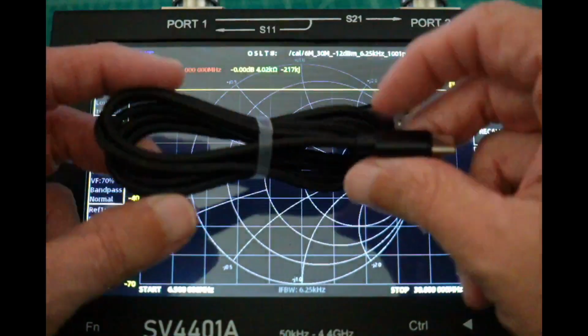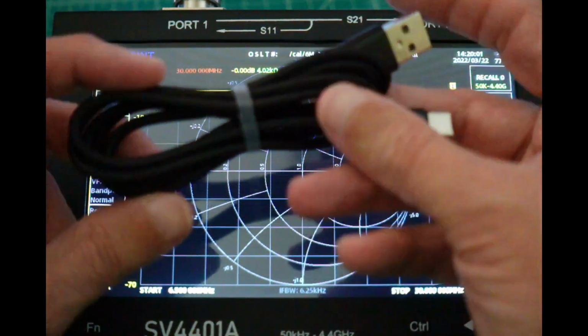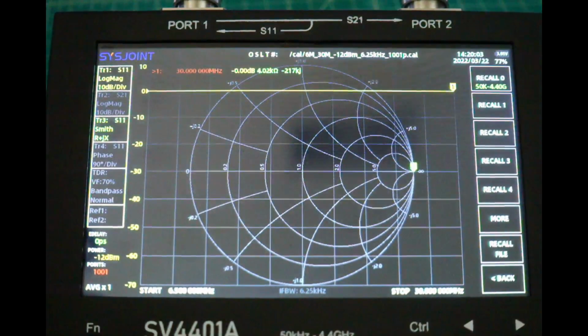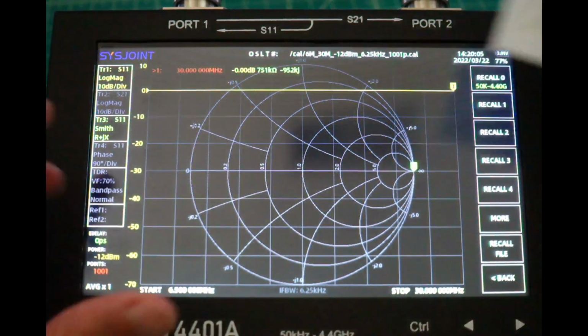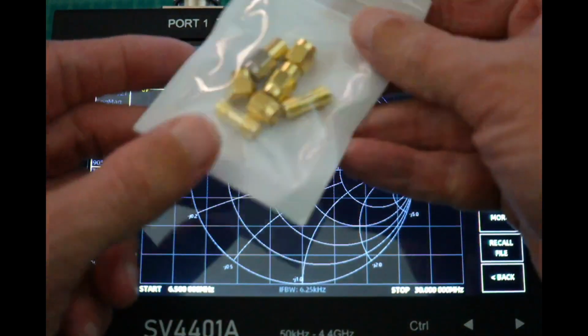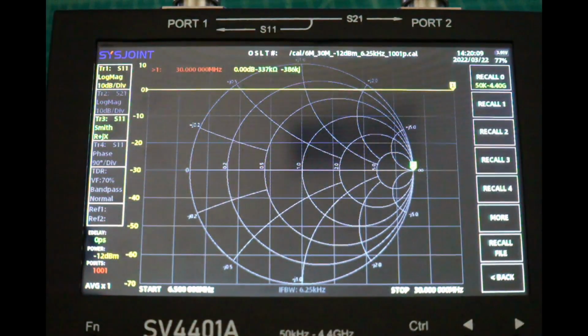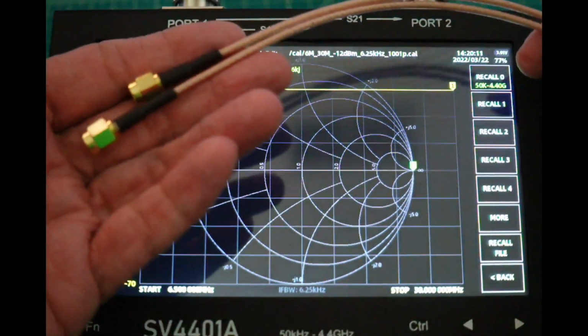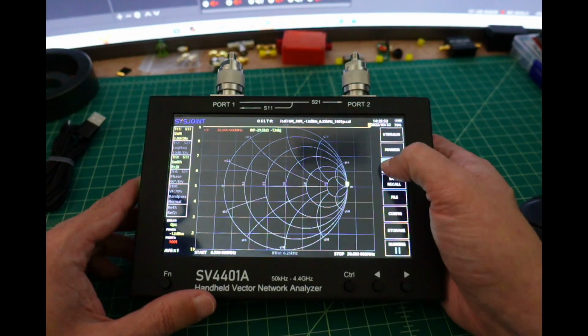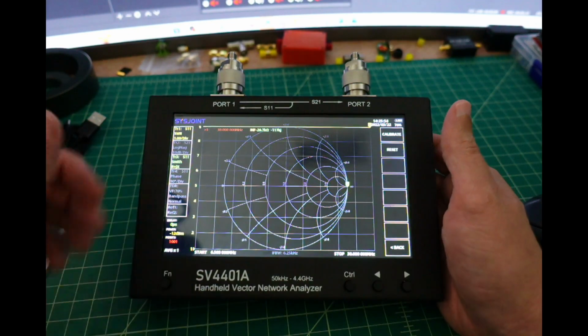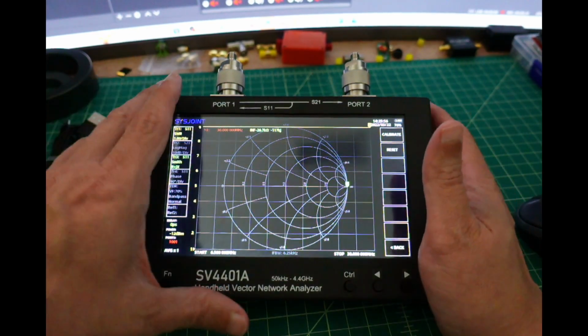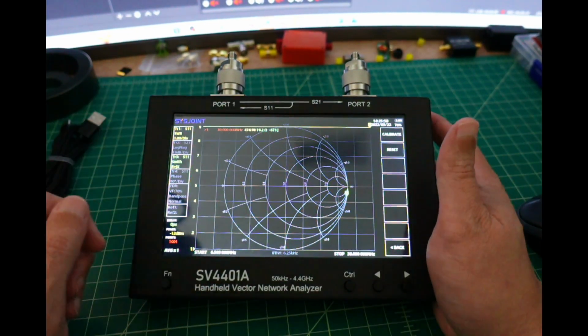So I wanted to mention real quick before we calibrate that this device did come with a USB-C cable for charging and connecting to the computer. But we're also going to need to use the calibration standards that came with the device, as well as the coaxial cables that came with the device. Okay, so what we're going to do now is go into calibrate, and then we are going to reset, which is going to remove any calibration from the device's current memory.